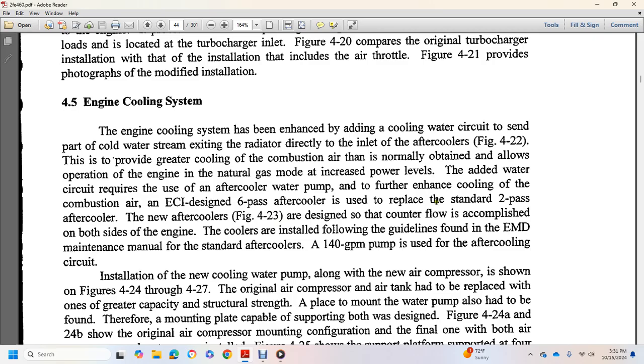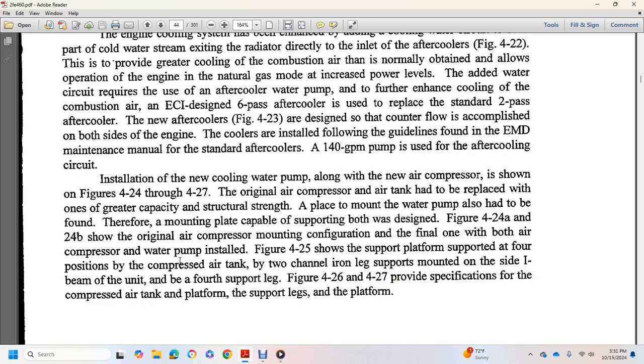Figure 4.23 shows the design for counterflow. Coolers on both sides of the engine are installed following the guidelines of the maintenance manual. The standard aftercooler flow is 140 gallons per minute.